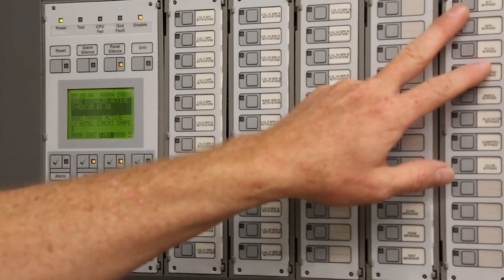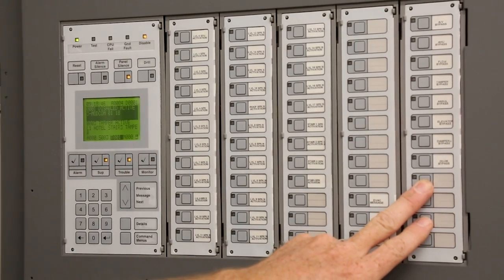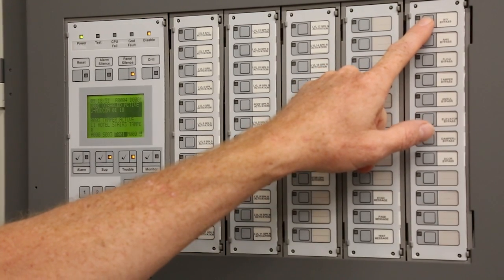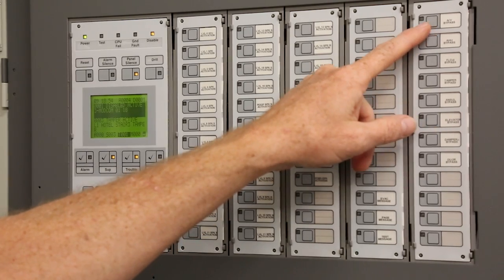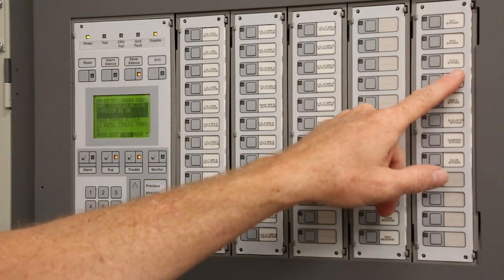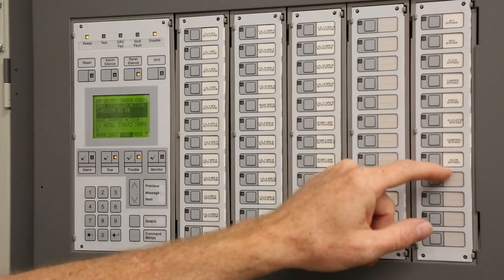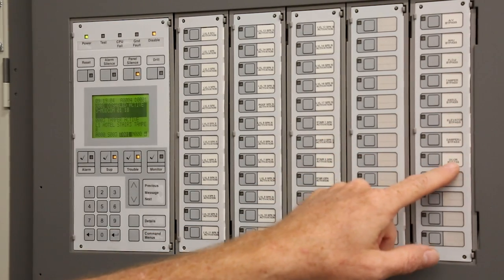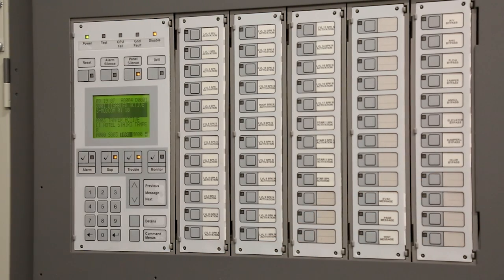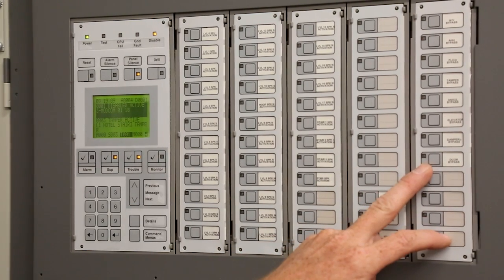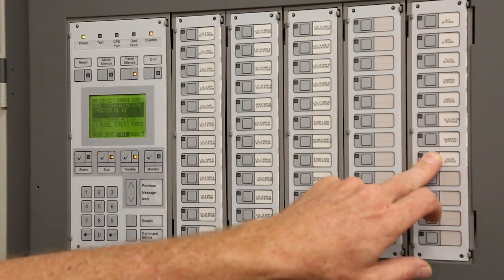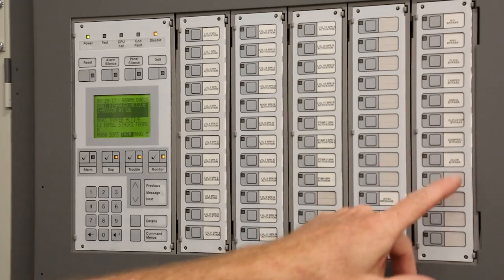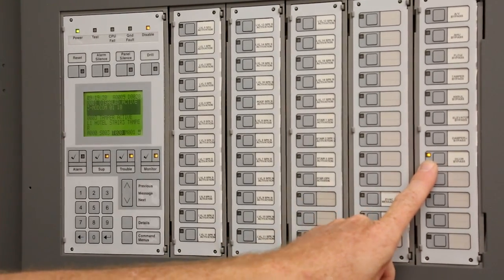Basically, on this side over here, we have bypass switches. So if we're doing any testing, you can simply hit AV bypass. It will light up and flash. And you have air handler bypasses, flow, tamper, Ansul, elevator, dampers, and door bypass. So for instance, if we're testing and we wanted to bypass the doors, you simply just push the button one time. Right now, it'll flash when it's activated right there.